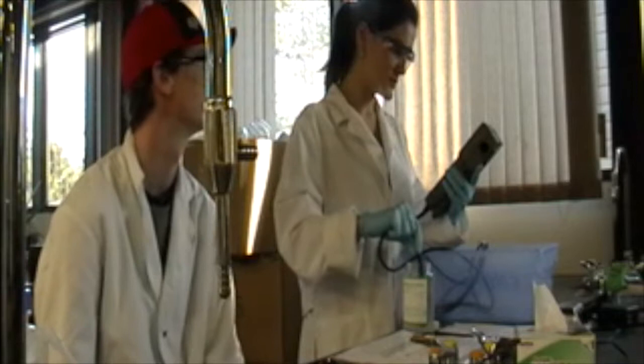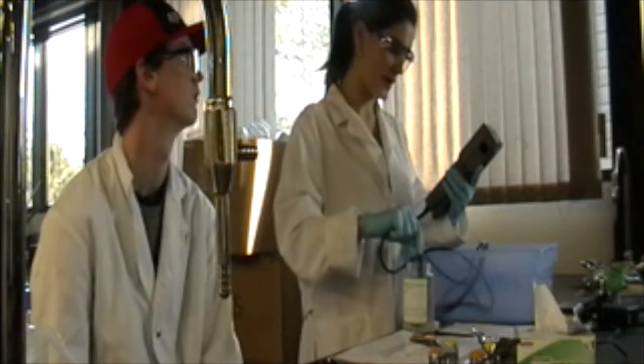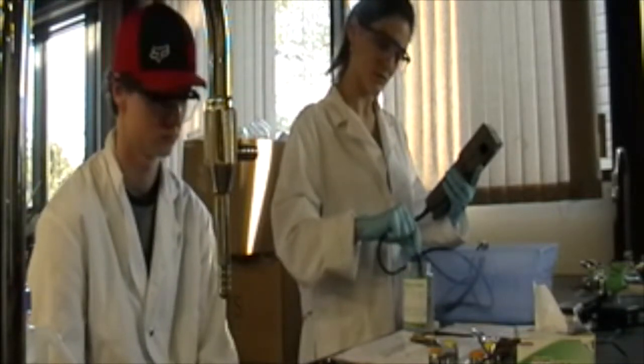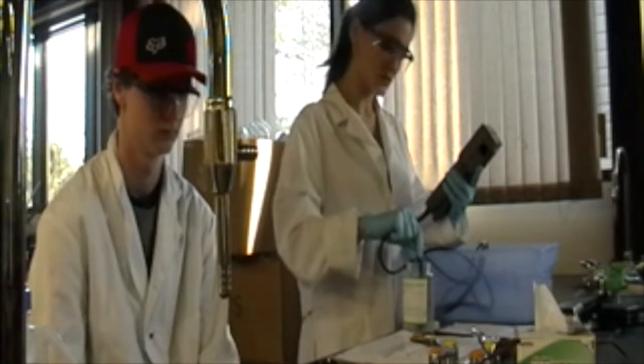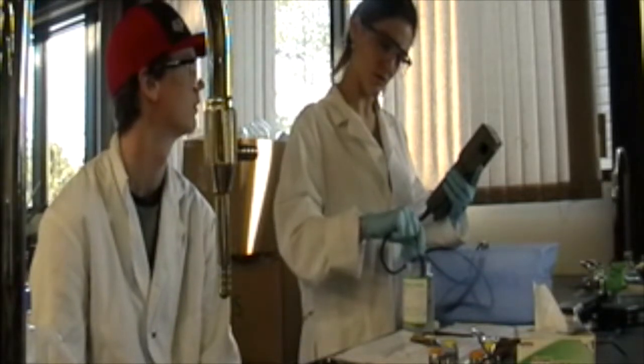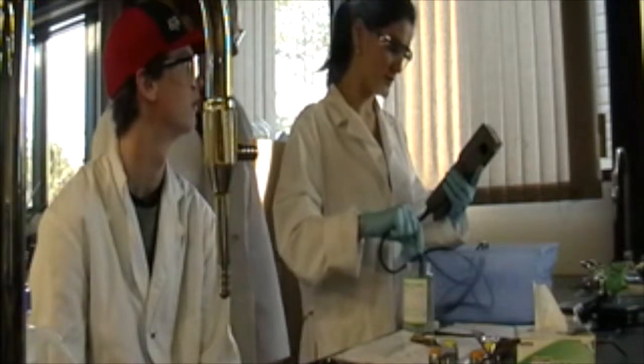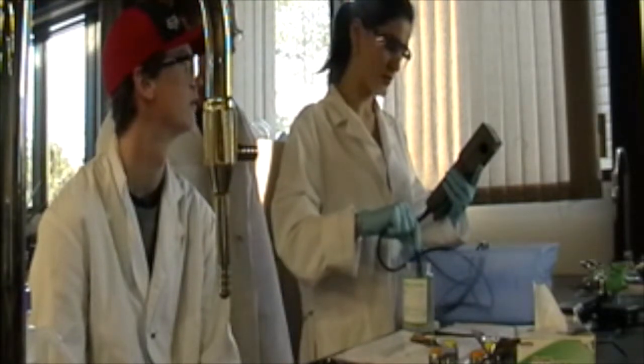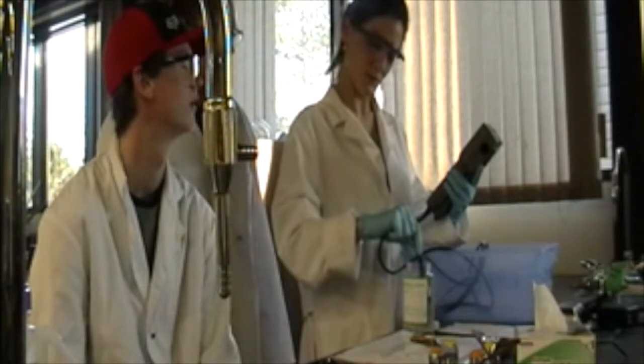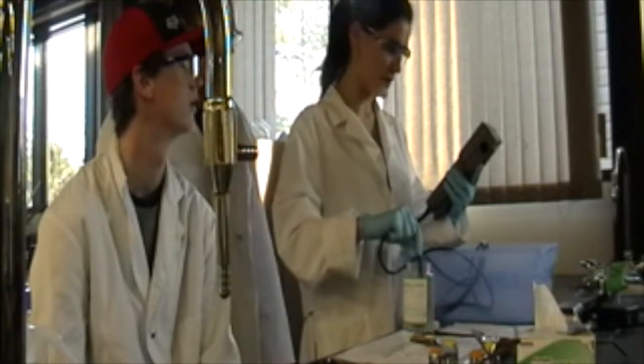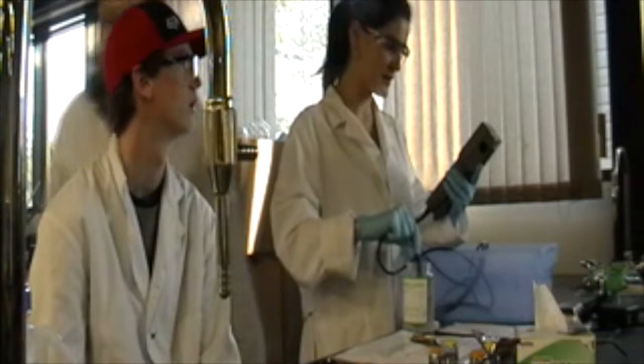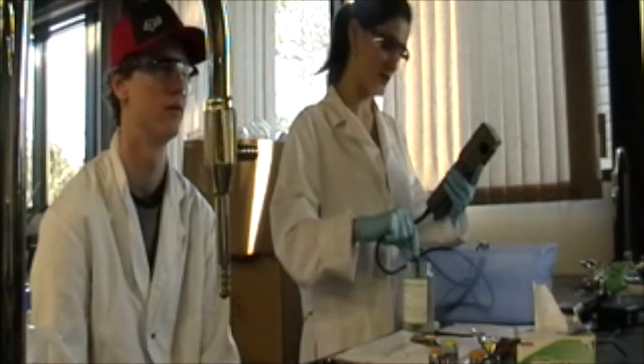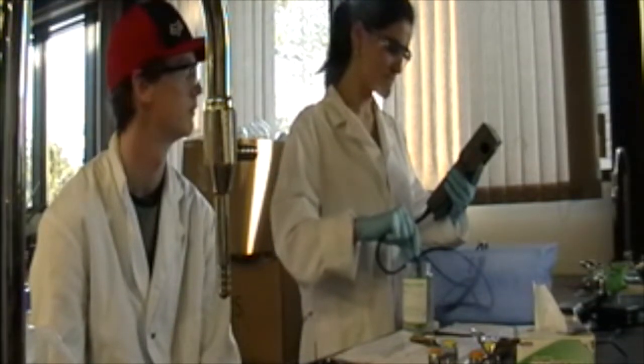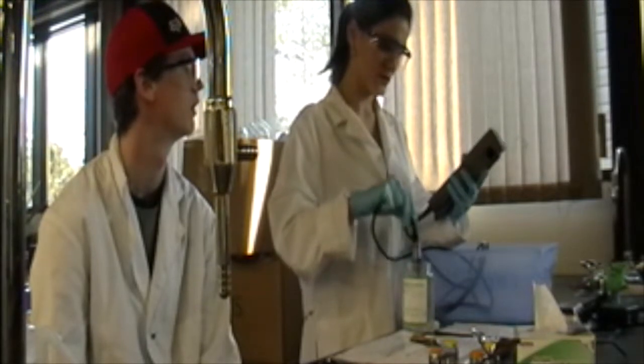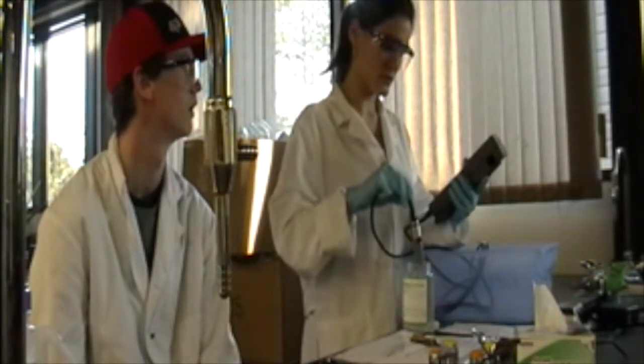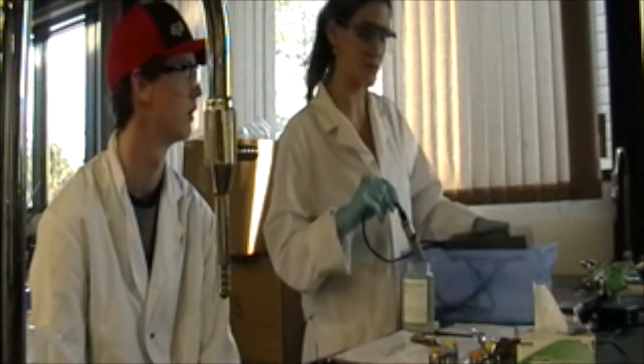Temperature seems to be stable at 18.9 degrees Celsius. It's not really changing. Give it another couple seconds. Alrighty, looks like we're good. So our conductivity reading is 515 microsiemens per centimeter. So now, take the probe out and we're going to rinse it with distilled water.